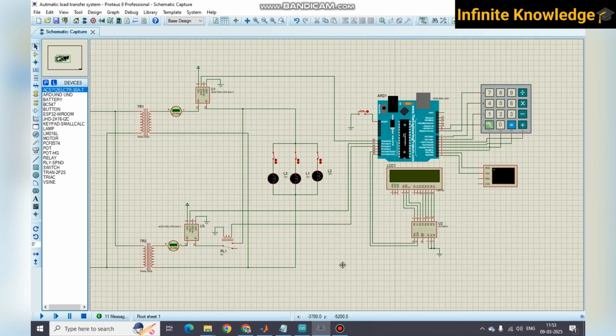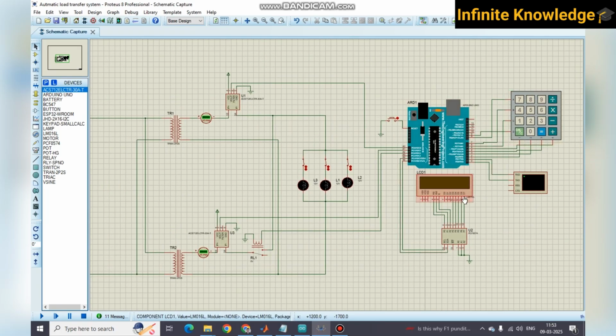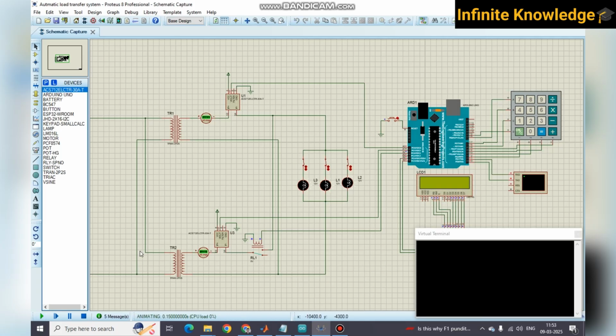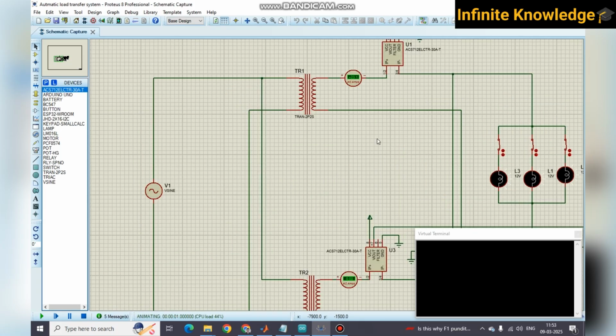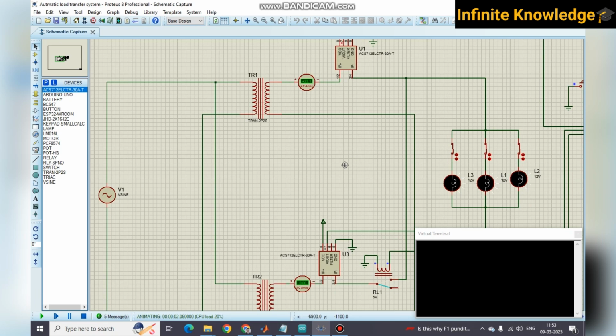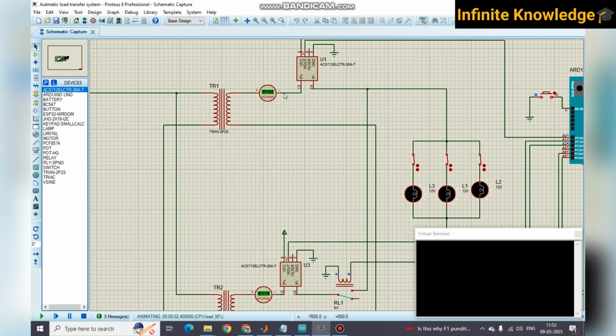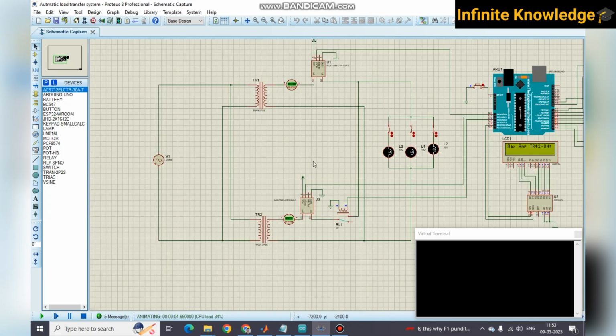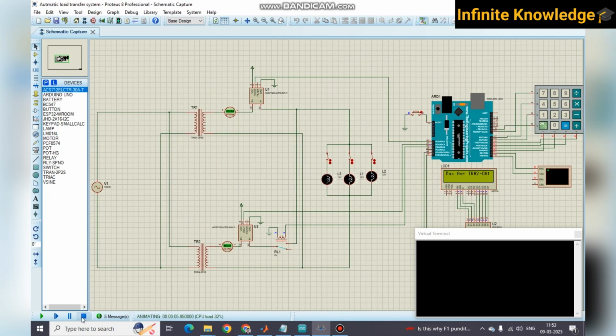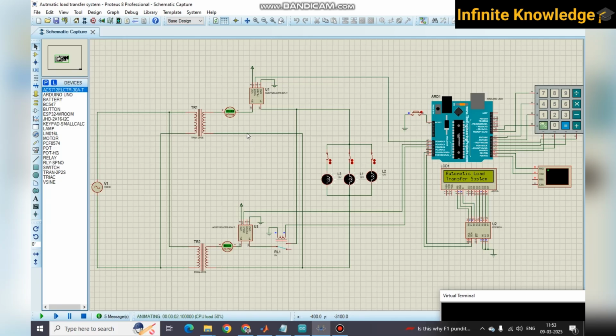You need to set that ampere value through this keyboard, and it will be displayed over here. When I start the simulation, only one transformer is in the picture and the second one is off, which is why 0 ampere is displayed over here. 23 ampere is continuously fed by this transformer on the secondary side. Now consider that this transformer has a limitation of 20 ampere on the secondary. So if the ampere is more than 20, then you need to turn on transformer TR2. When I start the simulation, you can see the automatic load transfer system on the transformer.